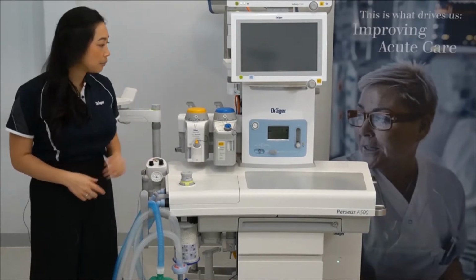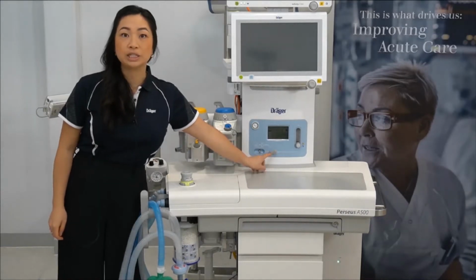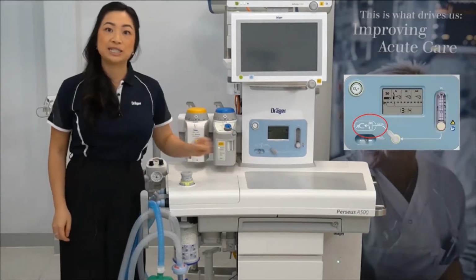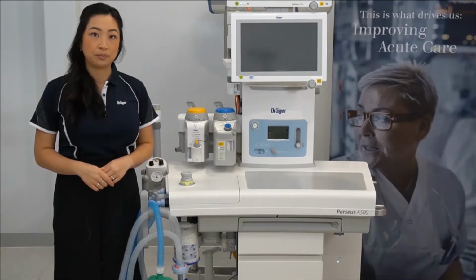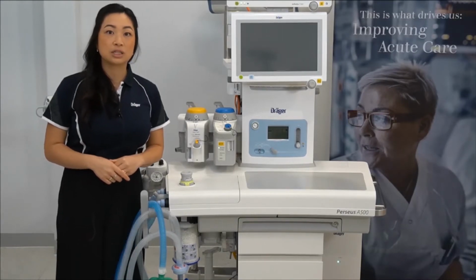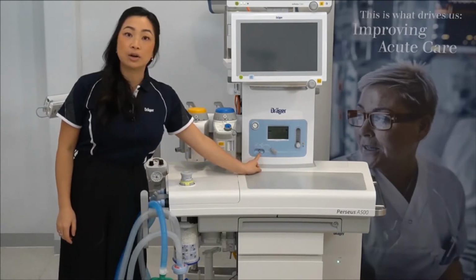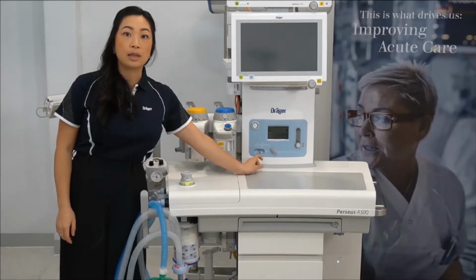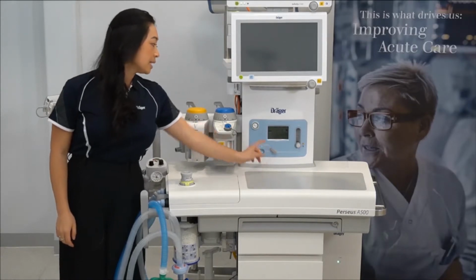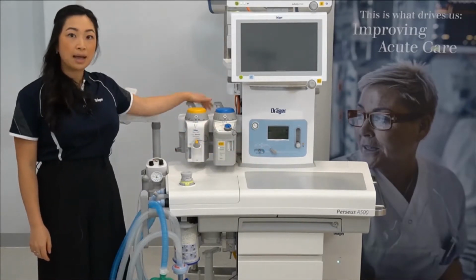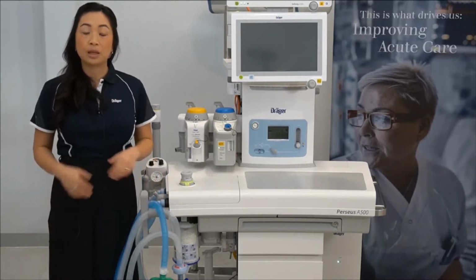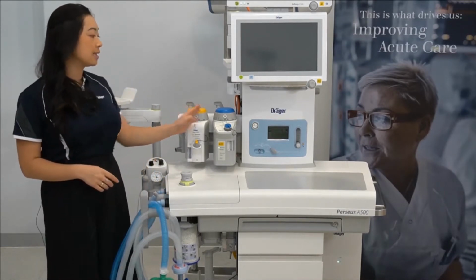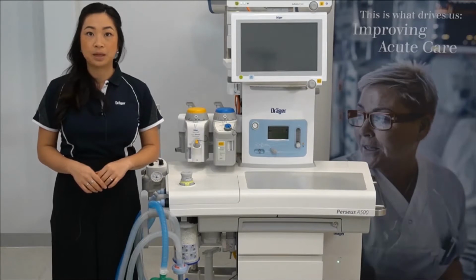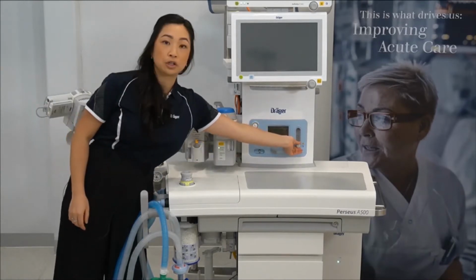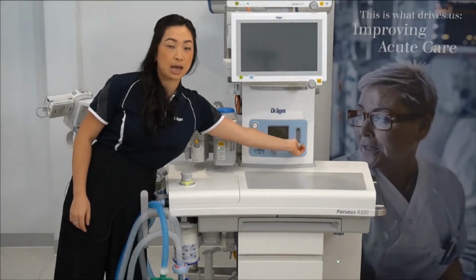To start, set your oxygen switch to Add O2, which stands for additional oxygen. Instead of the oxygen coming out of the auxiliary oxygen outlet nipple, the gas will be redirected into the vaporizer back bar and into the breathing circuit. Therefore, please verify your settings on the vaporizers. Then, open your flow control valve and set it to your desired flow.